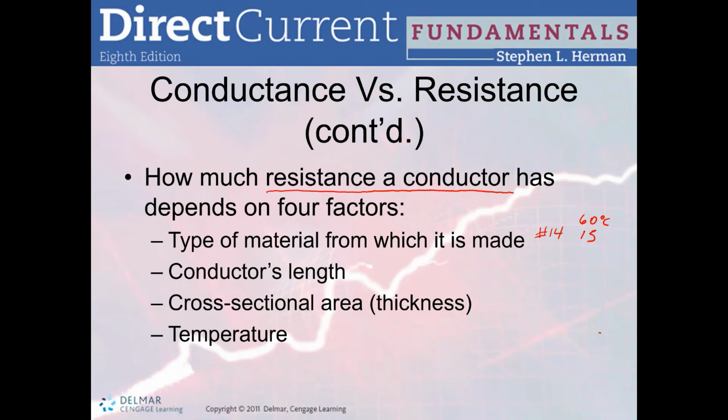Now, on the flip side, if we look at an aluminum conductor, the minimum conductor size for aluminum as per table 3, or table 4 in this case. I'm going to use table 4 in this case. Correct me if I'm wrong. The last time I saw it, I recall number 12 aluminum being 15 amps also at 60 Celsius.